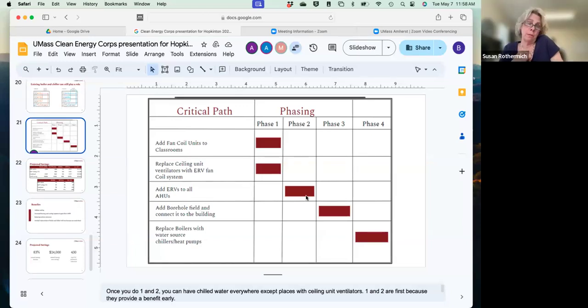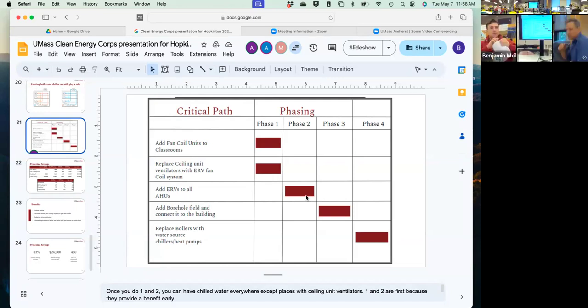And what's the risk? These units are, you know, at this point, 24 years old. So what is the risk of failure on the existing units if we just add the ERV to the AHUs? The risk would be wasting money on the ERV. Right? Because you just spent money on something that now, if you're replacing the whole thing, you would specify a new unit that has all the components all assembled by the same company. So the risk is throwing good money after bad.